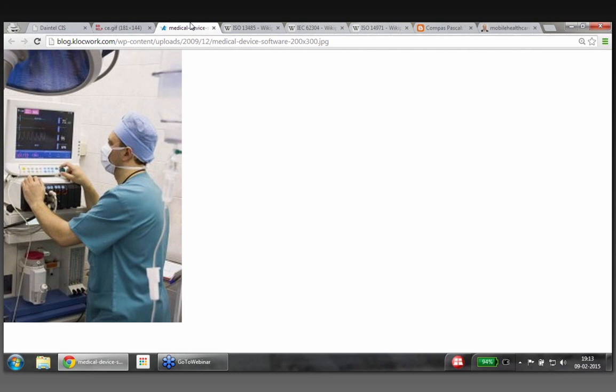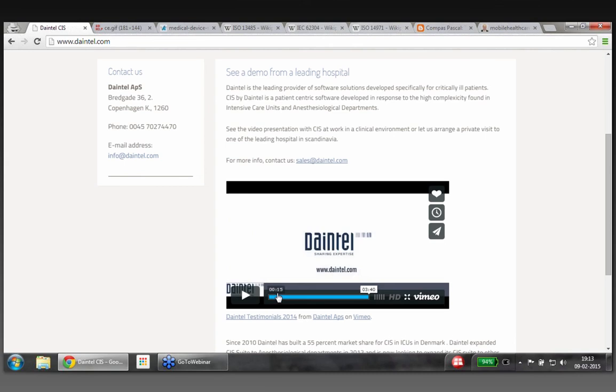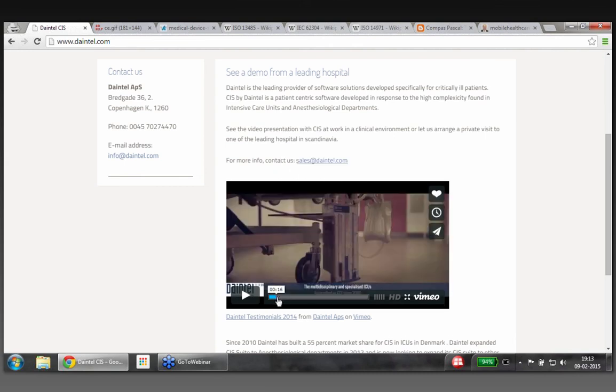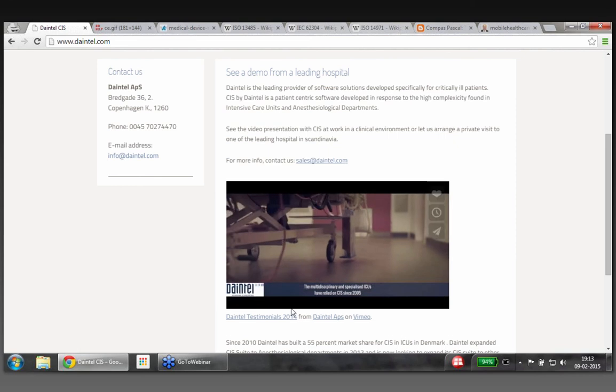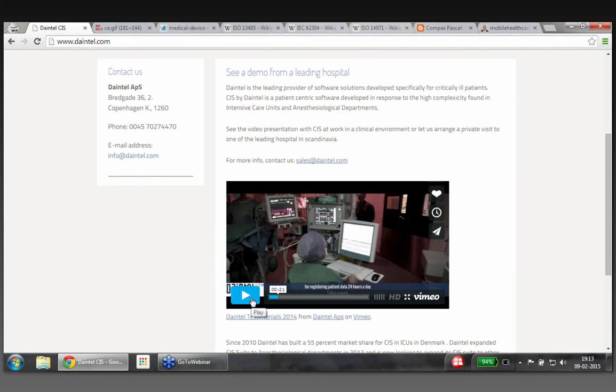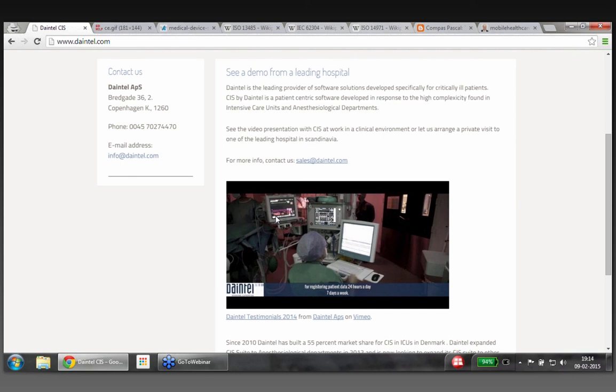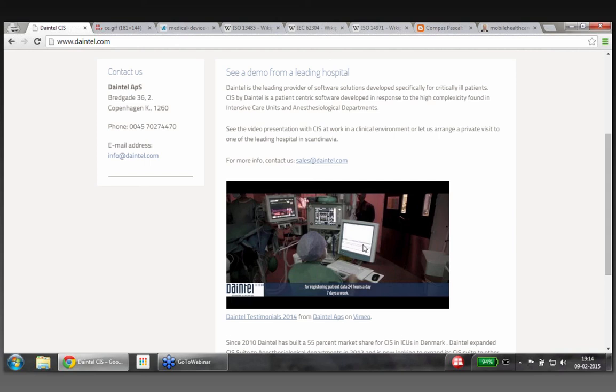But are there standards now as far as how computers are, or let's see, for computer systems to be used in medical industry, or are they considered interchangeable? Does it make a difference if it's where the computer comes from that's used as a medical device? Well, what you see here on the screen is a product that is made by a medical device vendor. So they will buy PC hardware and they will sell the entire box under their own name. But if I go back to the first one here and go back to the video, I don't know if some of you have seen it, and then I can show you. Here we have a screen or a situation where you have first a patient monitor. That is a specialized computer hardware for this purpose. The second one, I'm not really sure, but the third one is actually a standard PC, but it is washable. So this is because this is the surgery room, so they buy special washable computers and they're like $3,000, $4,000, $5,000.